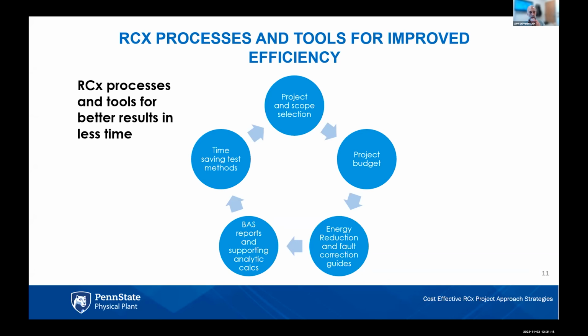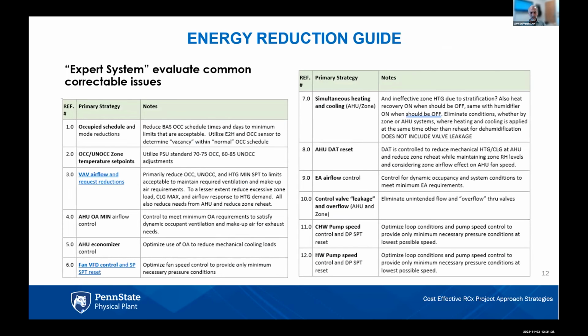But I really want to concentrate on two things: better use of the data that's in the BAS system, and the two guides we have, an energy reduction guide and a fault troubleshooting guide. Let me show those a little bit here. With the energy reduction guide, we're trying to build somewhat of an expert system to evaluate common correctable issues. I know the font's kind of small, but you see common issues like schedules and unoccupied set points, VAV set points, minimum airflow set points, DAT control, economizer, the things that you would expect to be on the list.